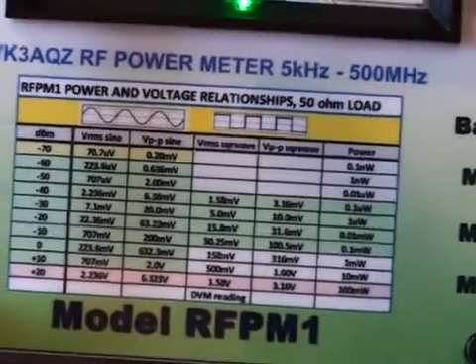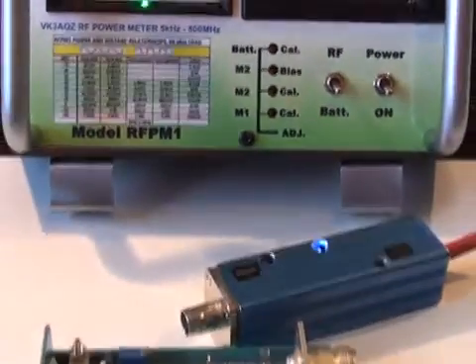The RF detector heads have a 50 ohm termination inside them, so all the measurements are done at 50 ohms.